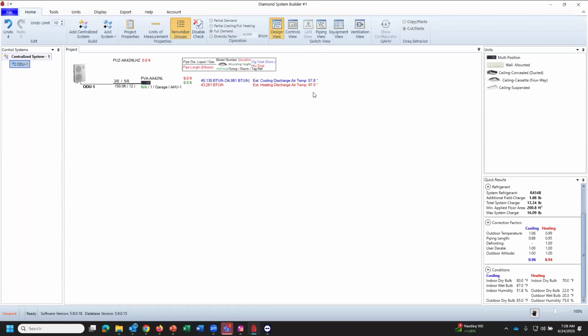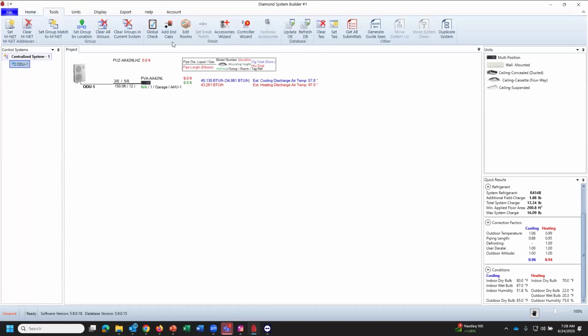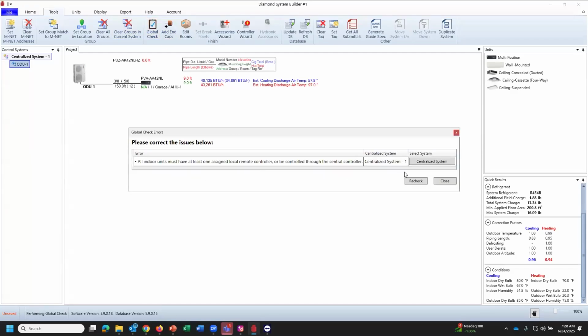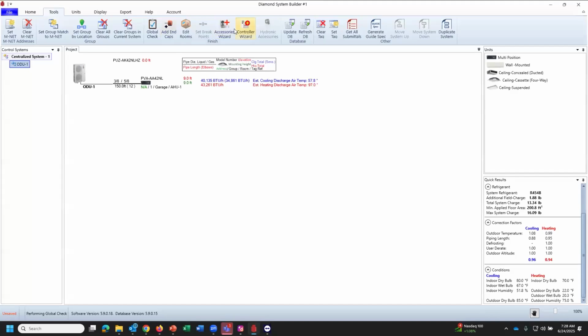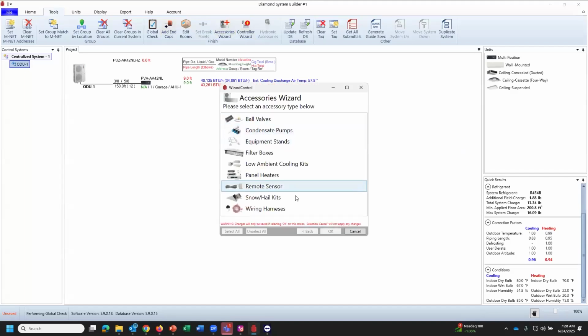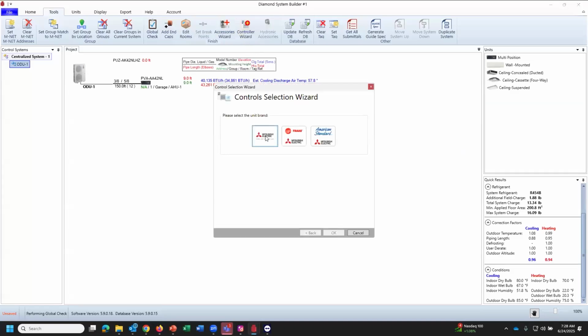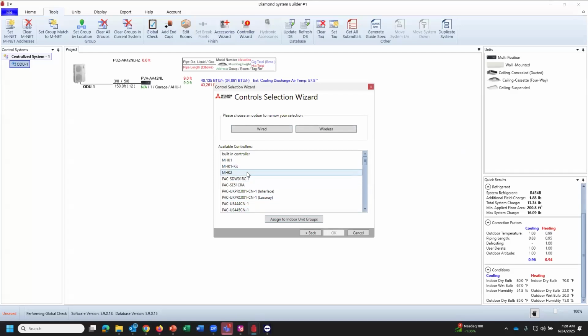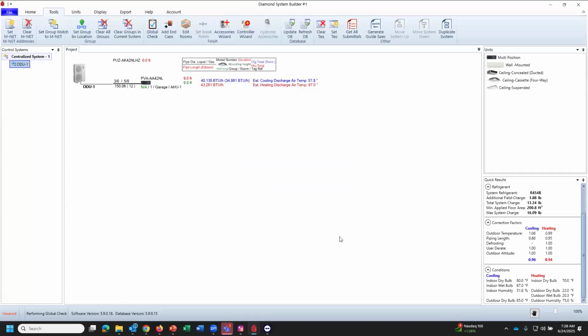This being a one-to-one system, one of the more important tools we can look for is the global check here, and it's going to tell you any possible defects you could have. In this situation, I never assigned a remote control to it. We can go through there and hit the accessories wizard, or the controller wizard, and say we're going to throw an MHK2 on here. Then it's going to basically tell me that all checks are performed successfully.